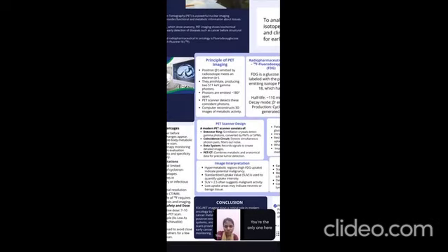The PET scanner design. A modern PET scanner consists of a detector ring, coincidence circuits, a data system, and PET/CT. The first one is the detector ring. The detector ring has scintillation crystals to detect the gamma photons, converted by PMTs or SiPMs.